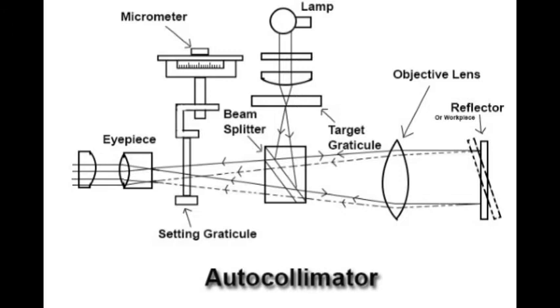Coming to the working of the auto collimator: the reflecting surface is the surface whose inclination is to be measured by using this device. The distance between the source of light and the reflected ray in the focal plane is measured using a micrometer microscope. First, the light source is illuminated and the rays of light diverge from the intersection point of the cross line target graticule, which is placed at the focal plane of the objective lens. The rays then reach the beam splitter, which directs them towards the objective lens. The objective lens parallelizes the light rays and they move towards the reflector.